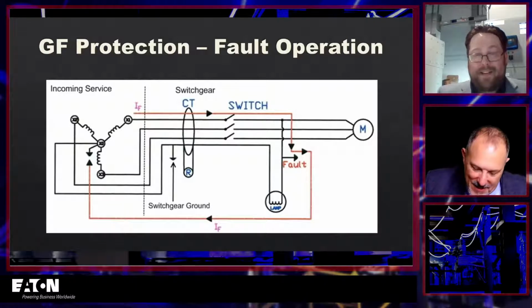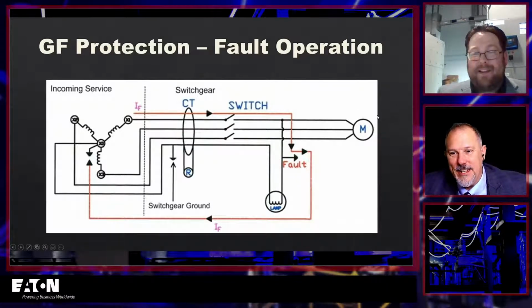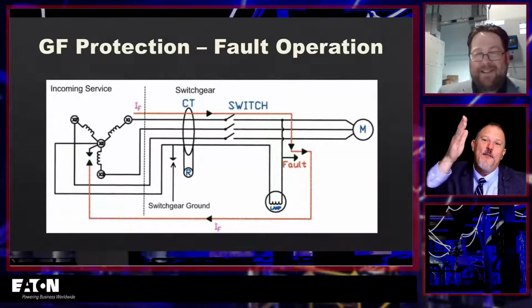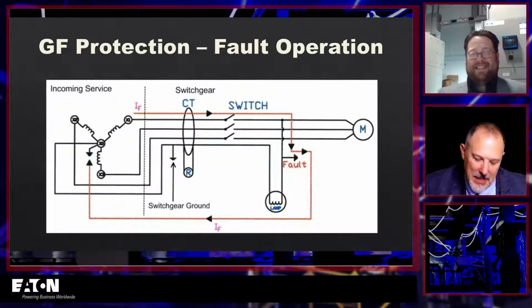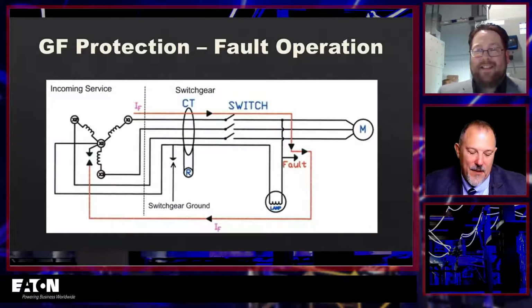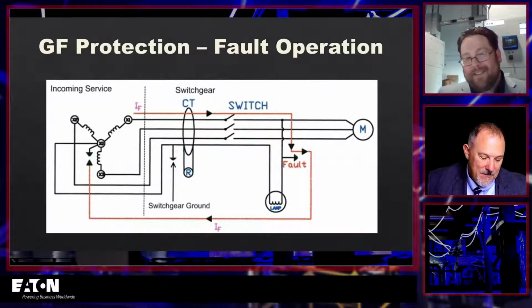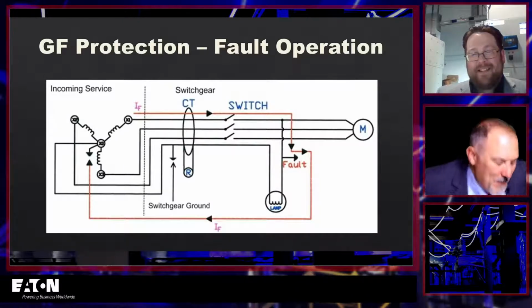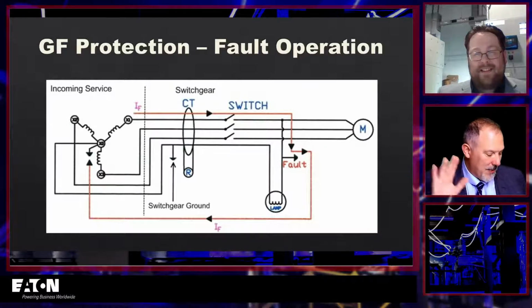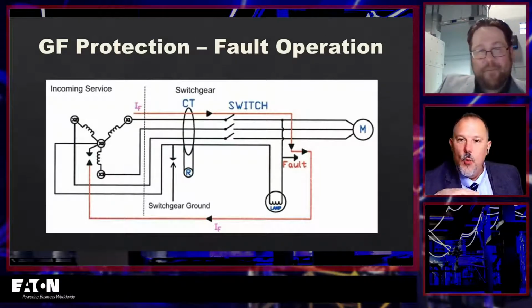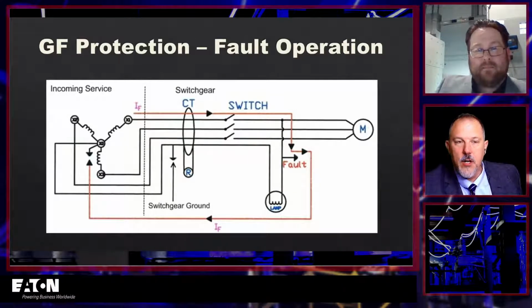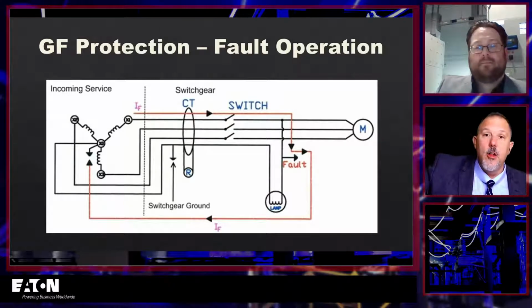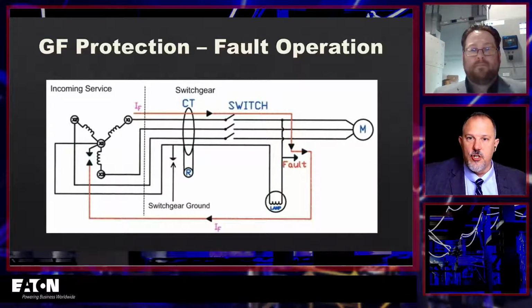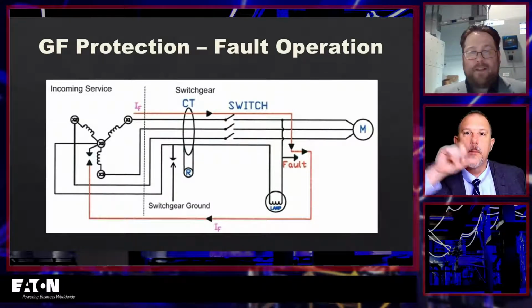And you know what? I don't know if my buddy Ryan Jackson is still on the line, but here's Article 250, 250.122. And Ryan, I liked your video. He did a video on 250.122, and I have a theory, because what you just said is so perfect. There's a section in here that says, when you increase the phase conductors because of voltage drop, right? Okay, say I've got a very long run and I increase my phase conductors because of voltage drop. What I have to do is increase my equipment grounding conductor proportionally the same.